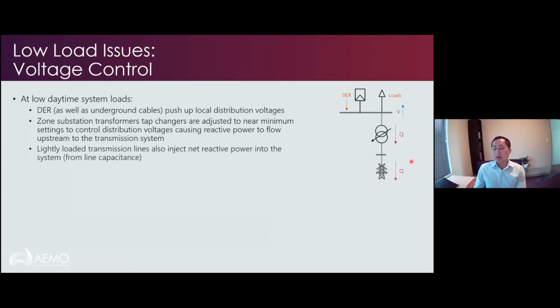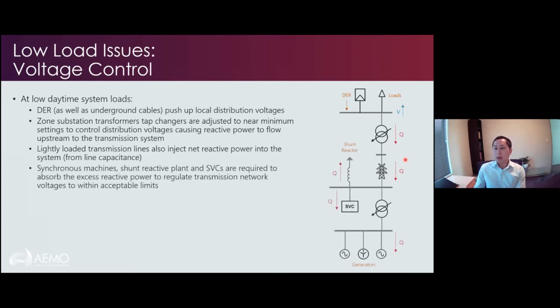And then also, because you've got not that much load on the system, all these high voltage transmission lines also have a net injection of reactive power. All the capacitance in the transmission lines is now injecting reactive power into the system. And then all of this has to be soaked up by synchronous machines like generators, as well as wind generators and solar generators, which can also soak up reactive power, SVCs and reactive plants. So here's a shunt reactor to make sure that the transmission voltages operate within limits.